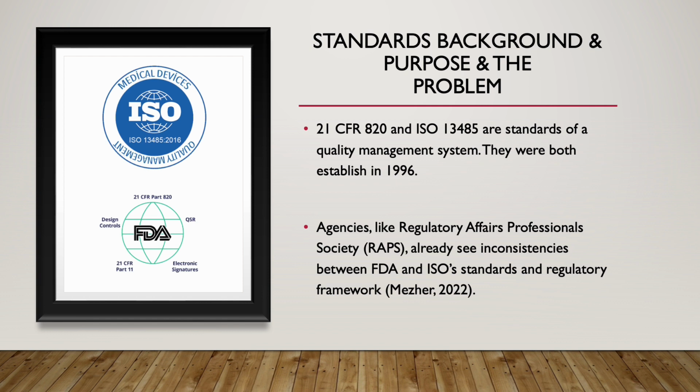An organization must be able to supply related services for medical devices that consistently meet customer and applicable regulatory standards, which is why ISO 13485 sets requirements for a quality management system. Unlike in the United States, where medical device companies are legally required to comply with the FDA quality system regulation outlined in 21 CFR Part 820, ISO 13485 certification is only required for companies that wish to market their medical devices in international markets like Europe or Canada.